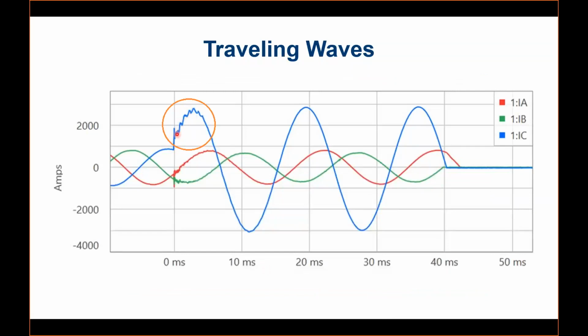After that, you may have a steady state fault current that may be larger, and you can detect it with the phasor-based, conventional methodologies. The traveling wave application will be utilized in a very fast manner, in a few milliseconds. You can think of less than a quarter of a cycle; traveling waves will die down. As you can see over here, there's a very high frequency transient, and it dies down within a few milliseconds.